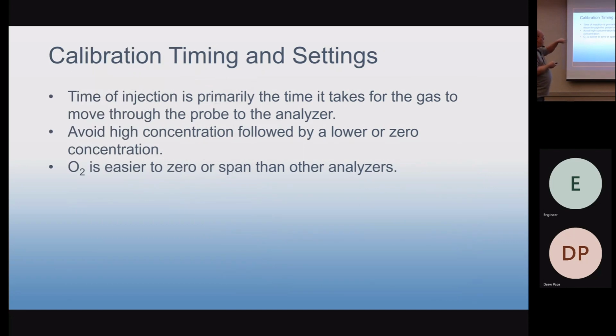So the timing is primarily based on how long it takes the gas to go through the system and fill the analyzer so that you can get a stable reading of the gas. One of the other things that plays into it is we've had very poor luck starting with a high concentration for an analyzer and then going to a low concentration. Just having good results from the calibration. Yeah, failing calibrations.